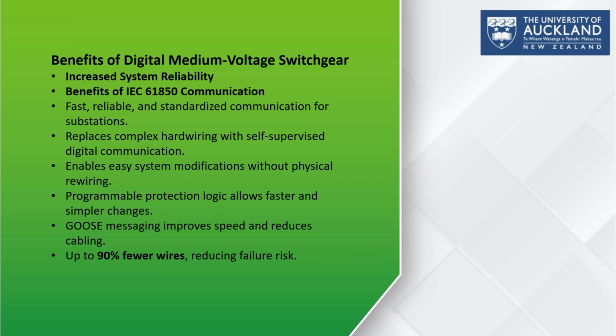It also gives us tremendous flexibility, so we can adapt or modify the switchgear without requiring physical rewiring or hardware changes. In IEC 61850, GOOSE messaging allows high-speed peer-to-peer communication among devices. This reduces cabling even further while improving response time, right?